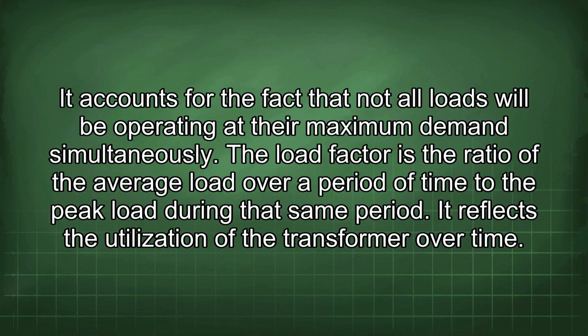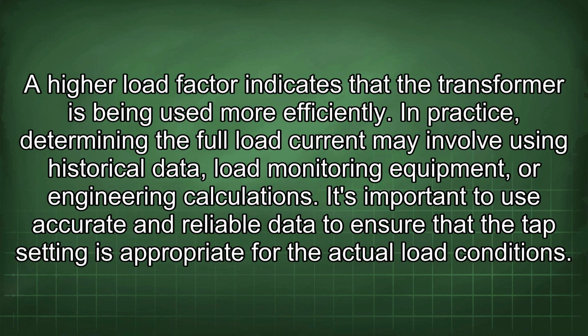It accounts for the fact that not all loads will be operating at their maximum demand simultaneously. The load factor is the ratio of the average load over a period of time to the peak load during the same period. It reflects the utilization of the transformer over time. A higher load factor indicates that the transformer is being used more efficiently. In practice, determining the full load current may involve using historical data, load monitoring equipment, or engineering calculations.